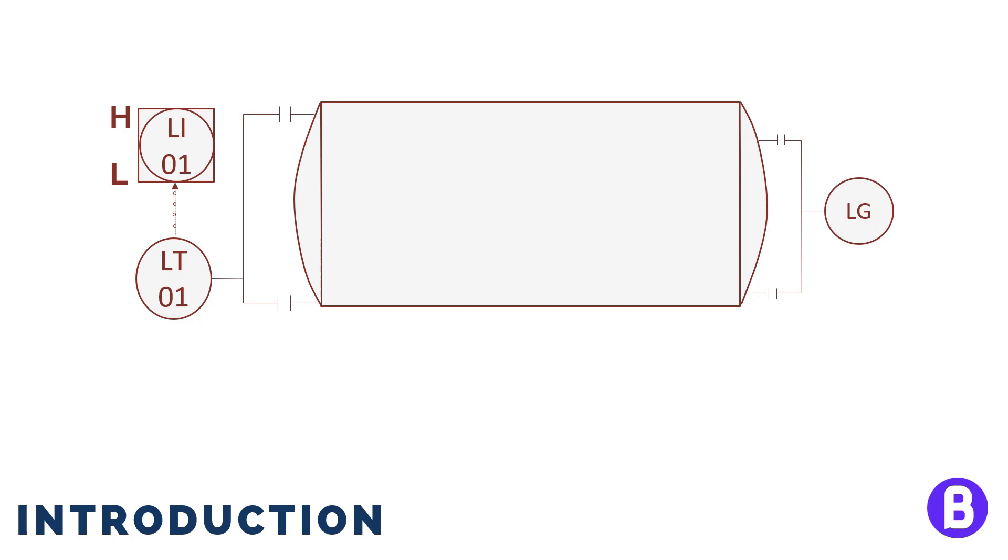If this level is used as a control parameter, then we shall see this level transmitter connected to a level control through an input signal, and the controller shall then process the reading and give an output. Based on the controller output, this shall send an output signal to the control valve, which adjusts its opening to keep the level in the vessel at the required set point.